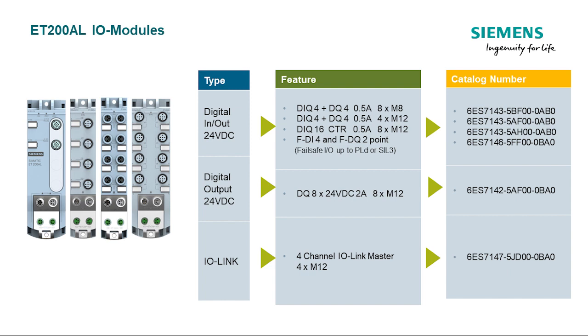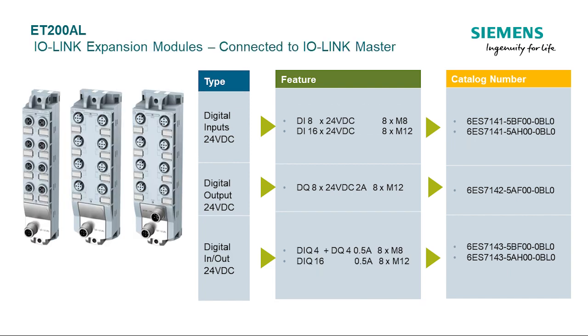The 16 DI/DO module can be used as a configurable 16-point module. If you choose to use the counters, each counter will have its own independent output on the module, and you will still have eight other configurable points. The next type is a digital output rated up to 2 amps per output, which is great for solenoids and other high-amperage loads. The last types are the I/O-Link master module and I/O-Link expansion modules, which can be used with the ET200AL I/O-Link master or any other approved I/O-Link master, allowing up to 16 points of I/O on a standard I/O-Link master channel.